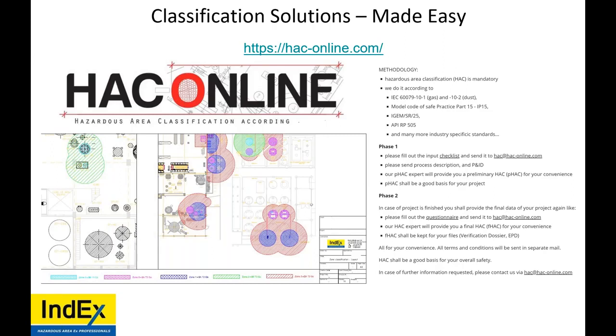Another question for the Ex d IIC enclosure. At what condition does there need to be a barrier gland? That one's a contentious issue. Three meters of cable or less? Or is the cable circular, compact? Is it non-hygroscopic?